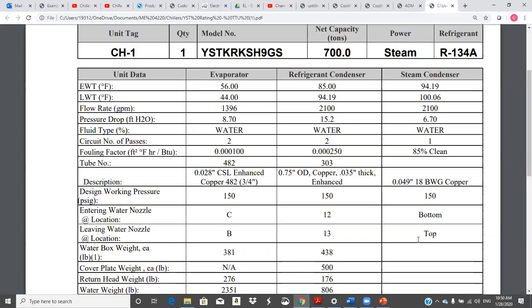Now, when you do these absorbers, you're going to need more. When you start simulating this thing, you have to be careful with these different chillers that you have the right size cooling tower, because the condenser water flow rate changes. The absorber needs more condenser water than this one. This one needs 3 GPM per ton. In some cases, those numbers are starting to change. These are kind of traditional numbers. And we need 2100. That's going to be the same 2100, I suspect.